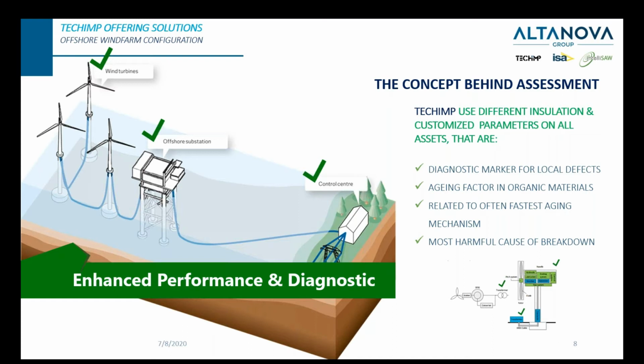And also, once we have those diagnostic markers, we need to figure out the aging factors in organic materials. Like if we see partial discharge, what does it mean? How do we get the result from the PD measurement? How do we determine which is the fastest aging mechanism? And how do we know what is the most harmful cause of breakdown? So all this information needs to be combined together to derive the final answer, telling the user what the risk is and what actions the user needs to take.